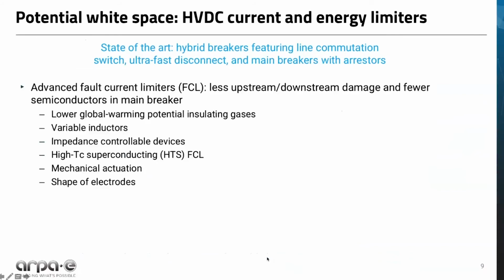The other aspect of getting to HVDC networks is current and energy limiters. Right now, the state of the art is a hybrid breaker with things like a line commutation switch, an ultra-fast disconnect, and main breakers with arrestors. What we're thinking about are advanced fault current limiters that cause less damage to other devices upstream and downstream, and that could reduce the number of semiconductors needed in the main breaker, thus reducing the overall cost of the system.